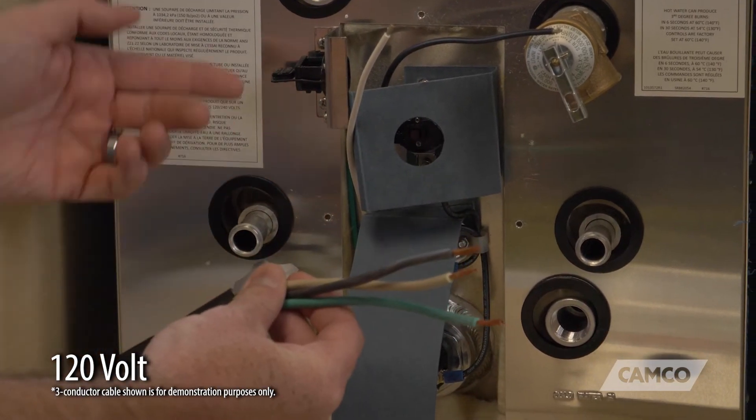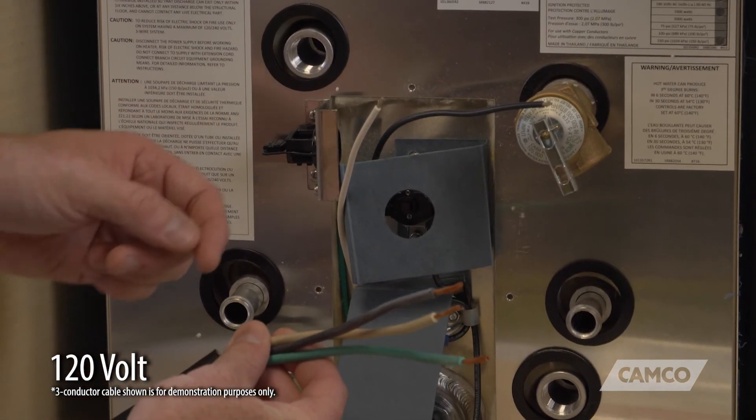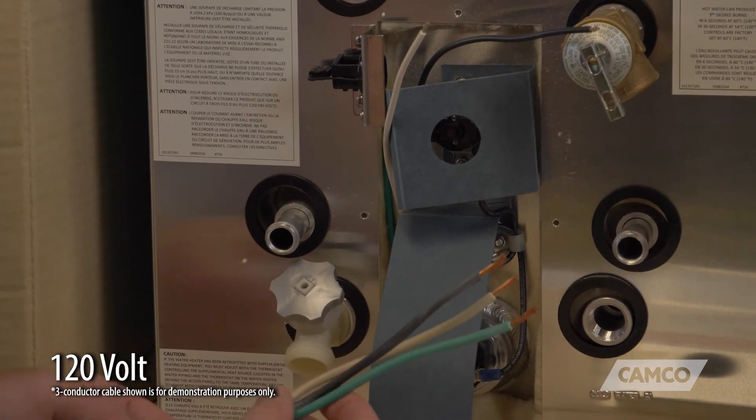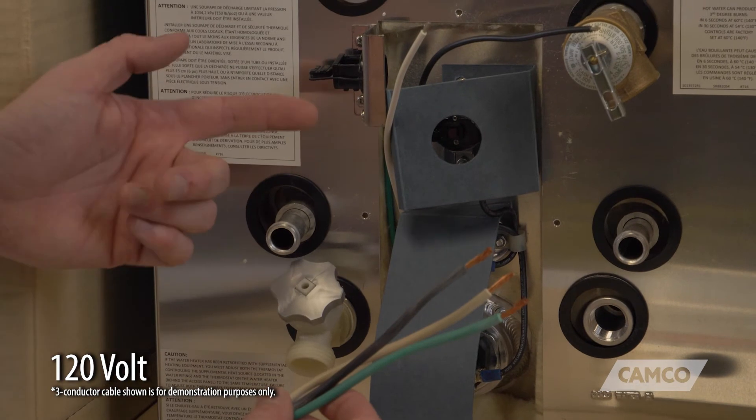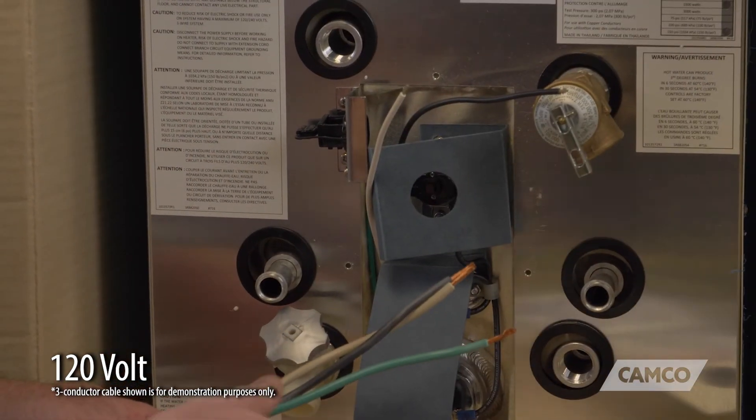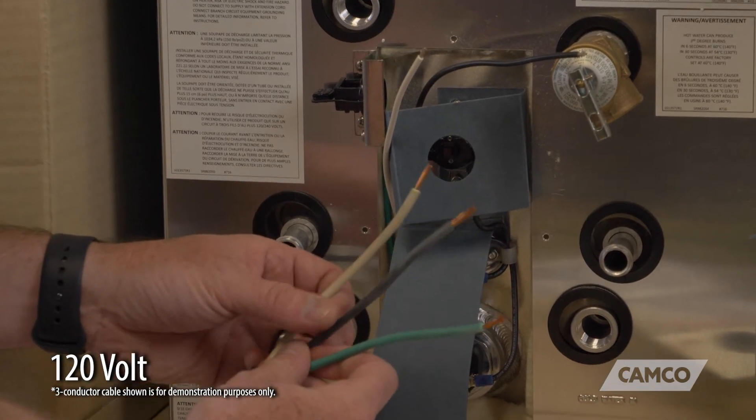You're going to run this wire through the strain relief clamp and you're going to make your connection. Depending on which version of Camco water heater you have, your ground connection may either be on the strain relief bracket or connected to the access panel. So you're going to make your connection with your ground, green to the ground.